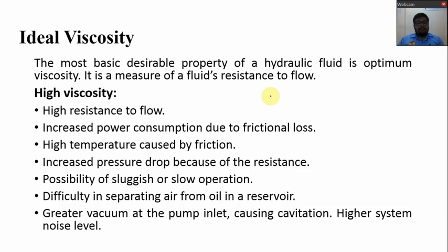Then greater vacuum at the pump inlet, causing cavitation, and a higher system noise level. As the flow of high viscosity fluid is very difficult and requires greater pressures, it will cause these types of problems.